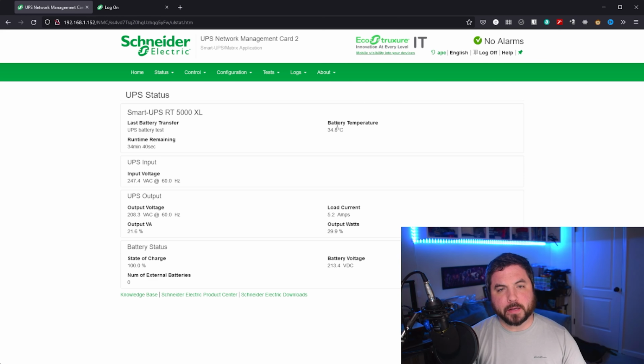Alright, and once you get into the system, in order to get web access, you have to plug into the network management card, and that could be just into your rack switch, and you're good to go. Take note of the IP address. I actually didn't see what the IP address was before I returned to my desk, but you can log into your router's management interface and look for something with the device name that starts with APC. And that should give you a good indicator of your device on your network. Once you find that, then you can log in, and the default username and password is APC. Very strongly recommended to change that for security reasons.